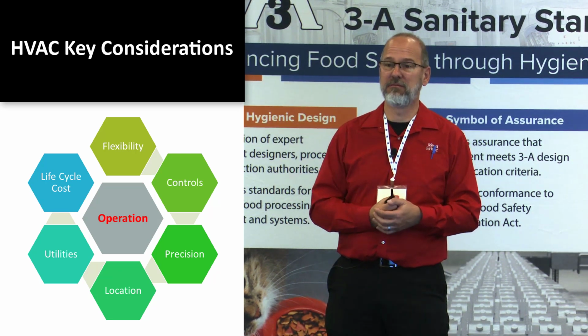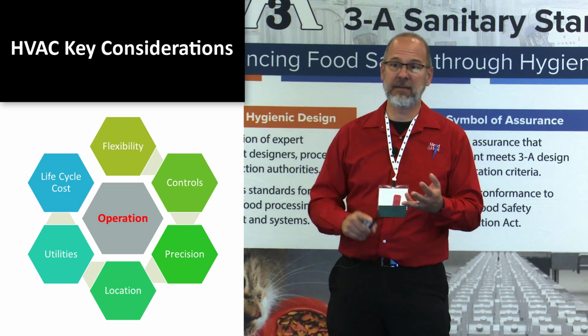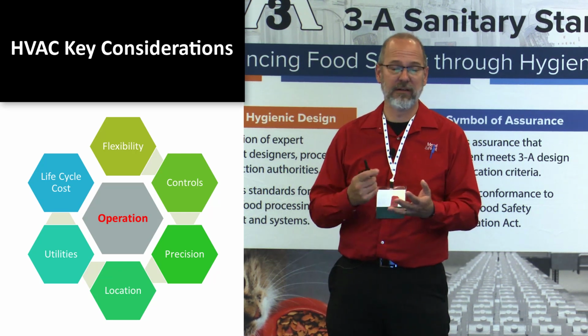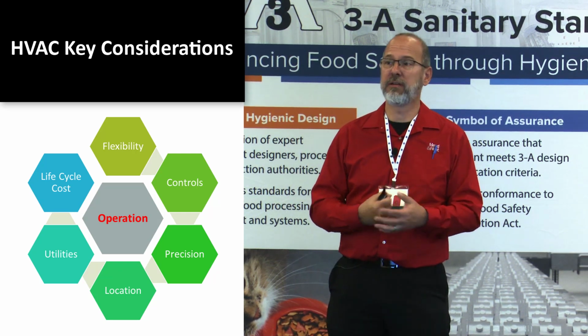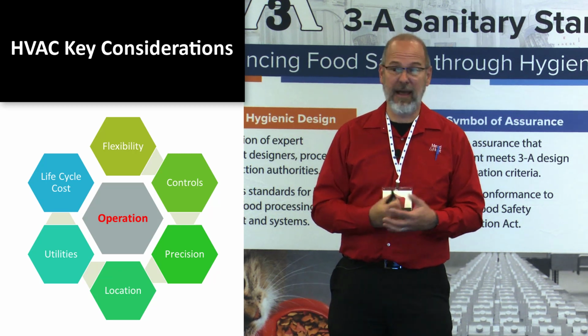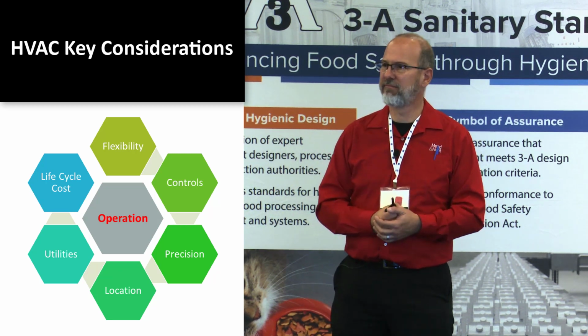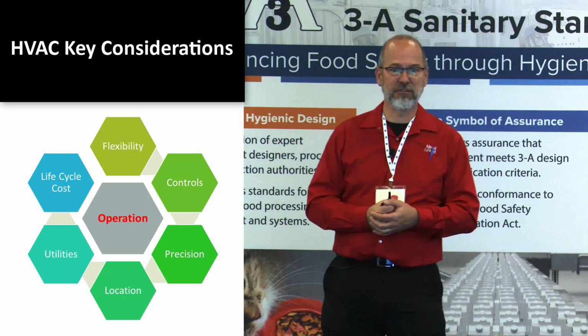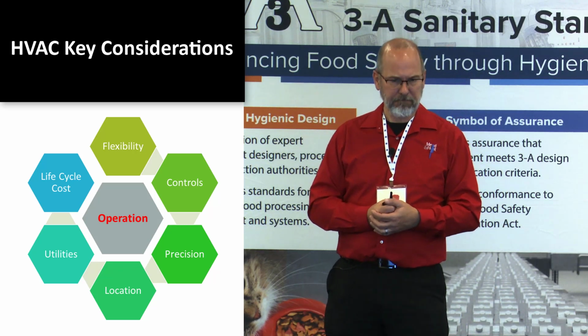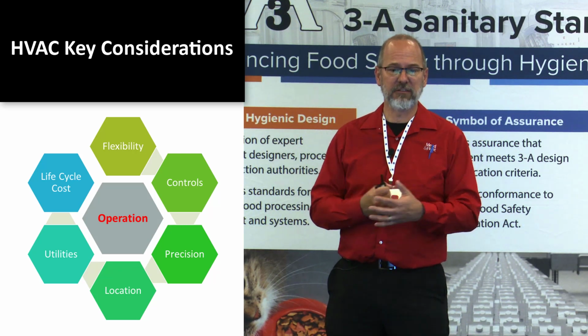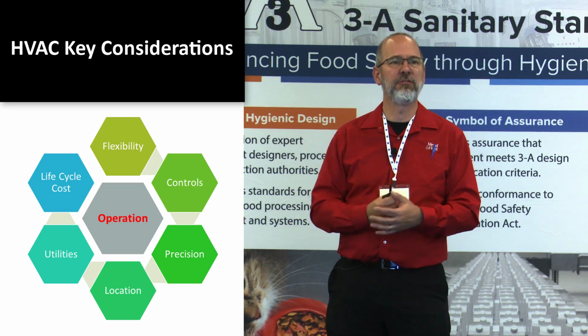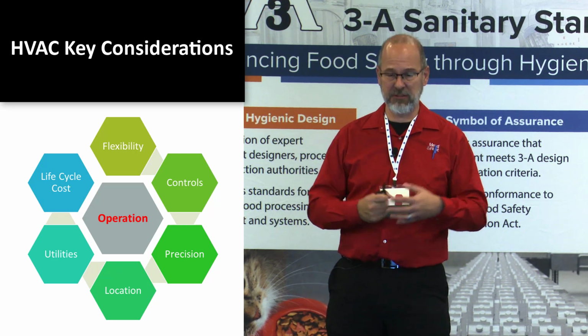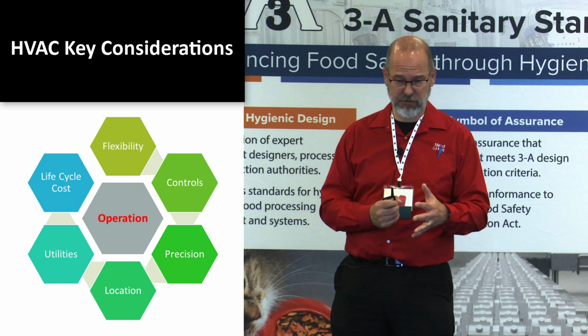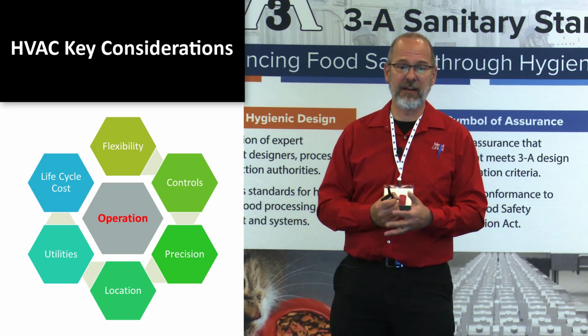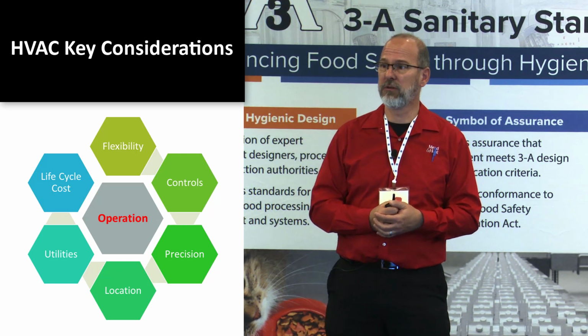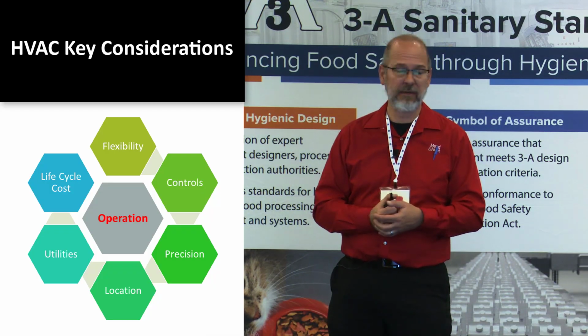Utilities, what's available? What are you going to use for heat? Steam, natural gas, hot water. What are you going to use for cooling? Ammonia, chilled water. Evaporative cooling, which generally in a food plant you don't want to do, but there's rare situations where it might make sense. And life cycle cost. You want to design these units to be as efficient as possible, because as much as their first cost is, the amount of energy they consume is huge. So you really want to make sure you're not wasting energy.